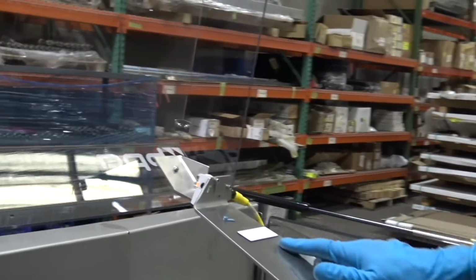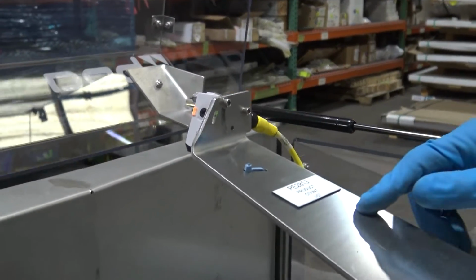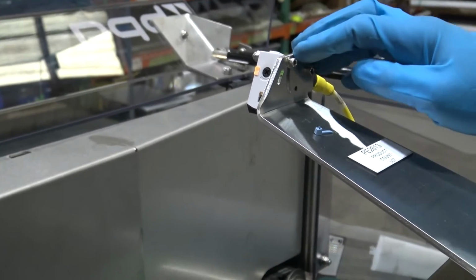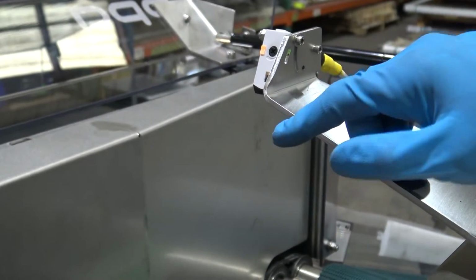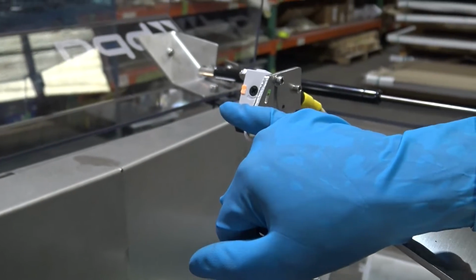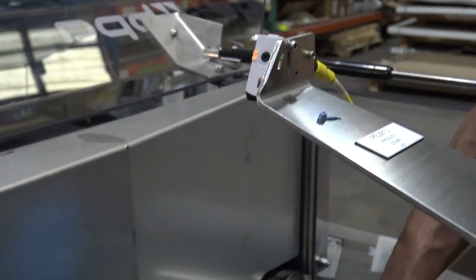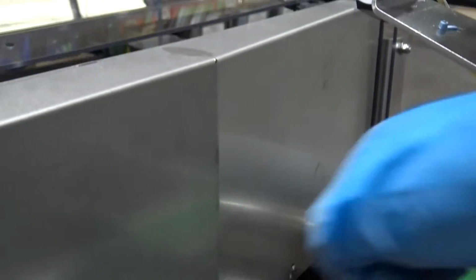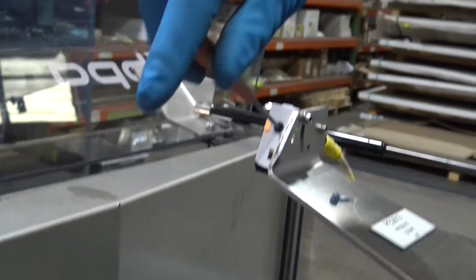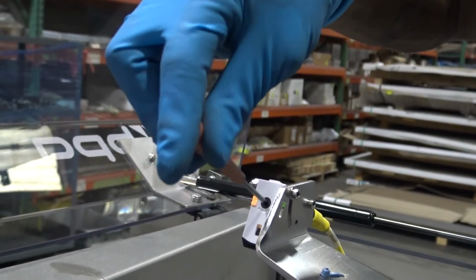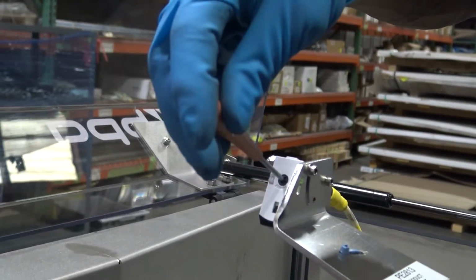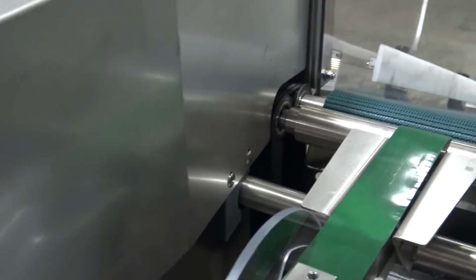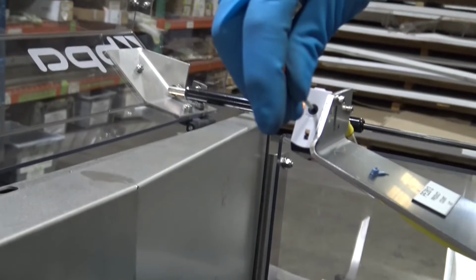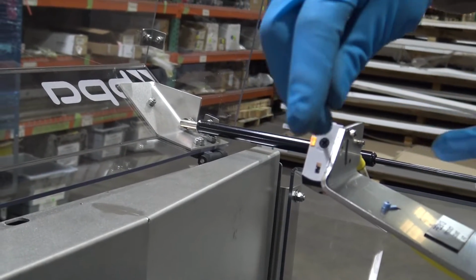This is the product count sensor. If you have to replace this sensor, when you get it out of the box and plug it in, you will see this yellow light. In order to get that yellow light to go away and adjust your sensor height to the belt, you want to get a screwdriver, stick it in, so that light goes away. Turn it clockwise, slowly, until that yellow light reappears.